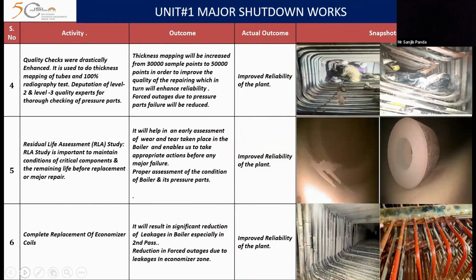Then quality checks we have done in the boiler tubes, apart from this 100% radiography test. So this has given us an opportunity to identify which tubes have thinned out, so that we have taken timely actions to correct that. Then RLA, as I said, in both boilers we have done to understand the residual life and what actions need to be taken to refurbish the boilers.